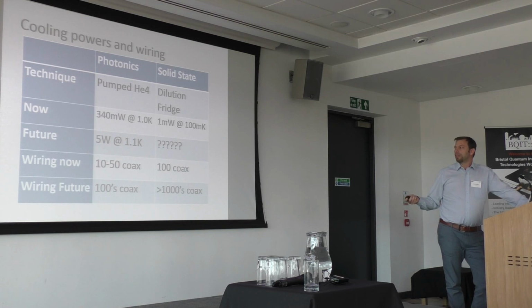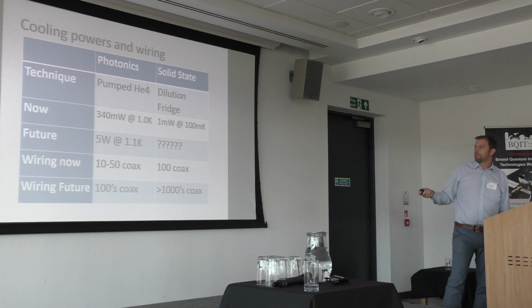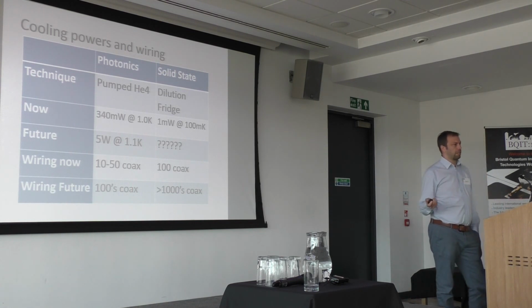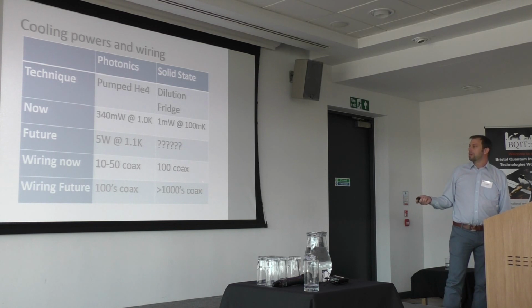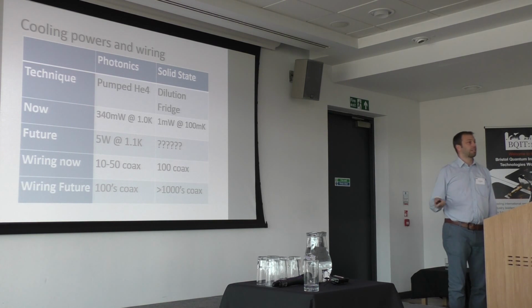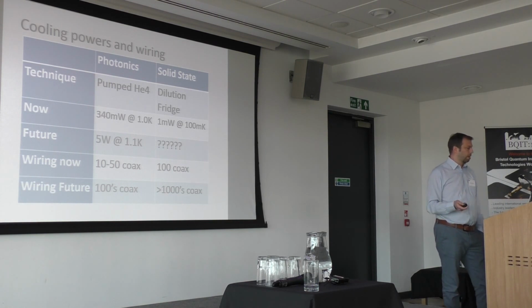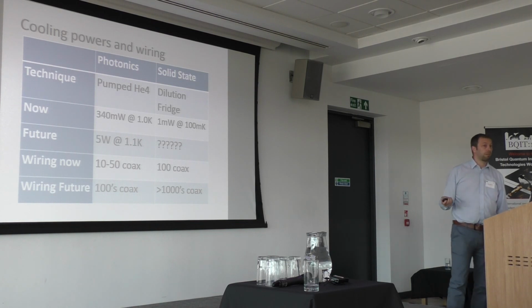Wiring typically runs 10 to 50 coax cables on a helium-4 system, up to a maximum of around 100 coax cables going into a dry dilution fridge. In the future, from what I've gathered here at Bristol, you might only need hundreds of coaxes on a helium-4 1 Kelvin system for photonic quantum computing, whereas solid state dilution fridges may need thousands of coaxes. That in itself is a huge problem, and may mean scaling photonics is a far better option in the long run.